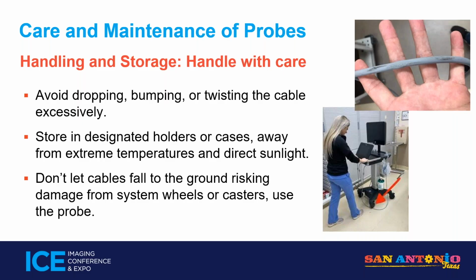An example I like to point out is a brand new Philips EPIQ. If you guys have had them or seen them in your hospital, the probe cable goes from the bottom of the probe down to the ground and lays right on the ground in front of the caster, then comes up where they hang the probe. That sounds bad already, right? But what you don't realize is if you move the machine in this configuration, you roll over that cable, and it yanks a connector out of the front of the system.